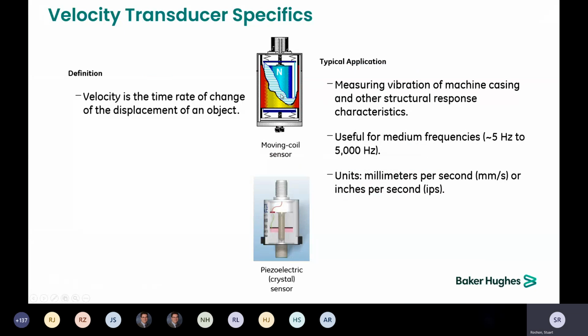Velocity pickups are the spring, coil, and magnet type. They are self-generating. They supply their own power. Basically it works on the principle that a magnet moving through a coil of wire generates an electric current. By having that coil of wire on a set of springs around a permanently mounted magnet, as the machine vibrates, the inertia of the coil causes it to oscillate around the magnet, and we measure that current and calculate the velocity of the vibration from that.